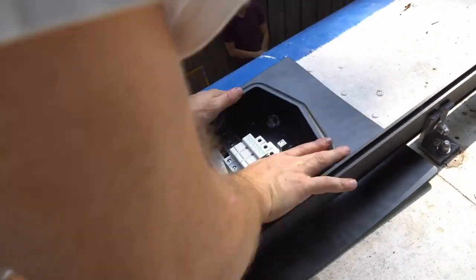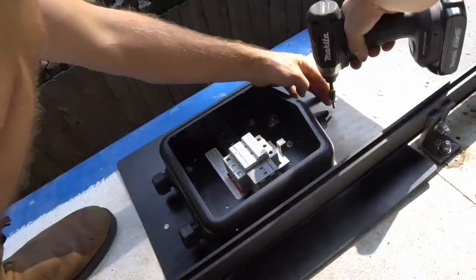I think it's really smart to just totally max out the solar you can put on your roof. The 3200 watts of solar panels are configured two series, four parallel, and they all go into the solar deck combiner box that you saw us install. From there they are fused, and then go to a breaker box. That breaker allows us to turn off the power coming from the solar panels.